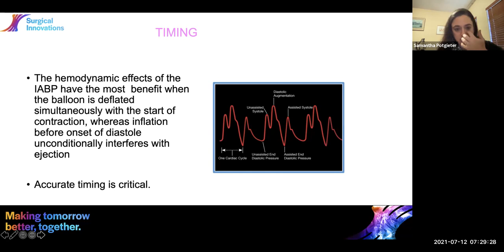Right, so we touched on just briefly the introduction of fiber optic in 2007, I think it was, and how that has improved the delivery system of how the balloon pumps work. The fiber optic sends information back with the speed of light to the pump. So it's measured at the little tip on the catheter, and that sends information back to the pump, and the software takes that information, and that information then helps towards the timing. So if we were using a conventional balloon with a transducer, as those of you that work with transducers know, you get that drift and you're having to zero your transducer so that you're getting an accurate reading. We don't have this headache with fiber optic, and this makes the delivery system of the balloon inflation and deflation and the support to the patient that much more accurate, because, as I say, literally with the speed of light, that information is carried back and forth.